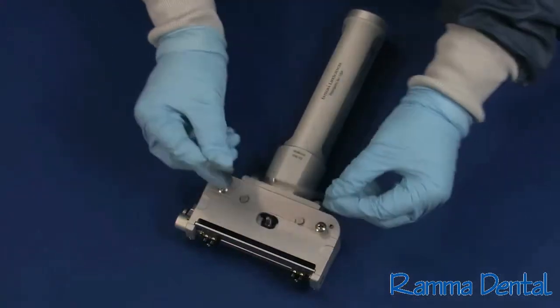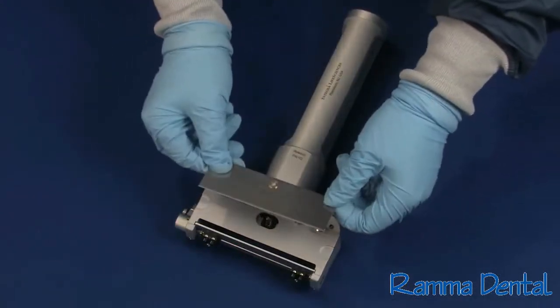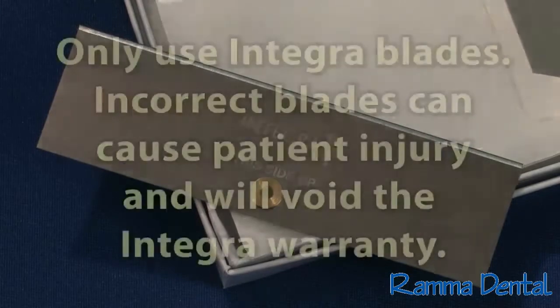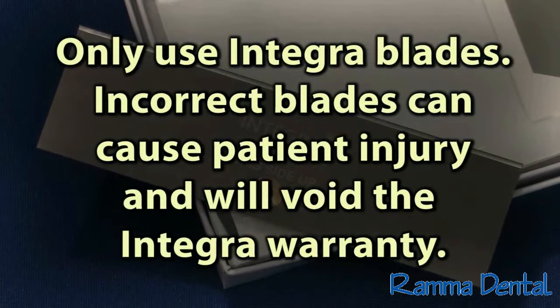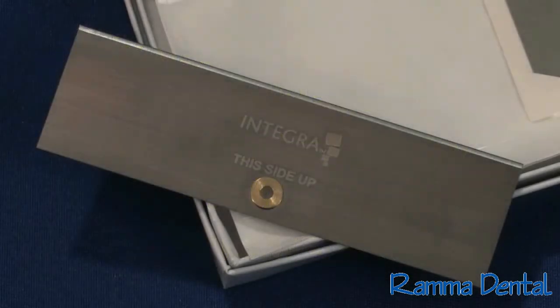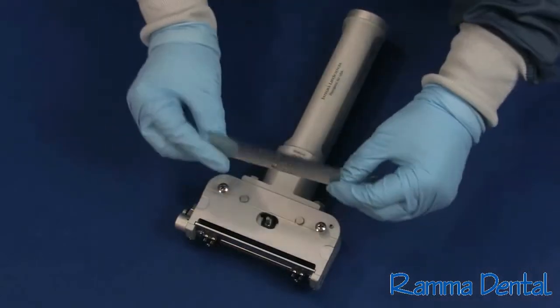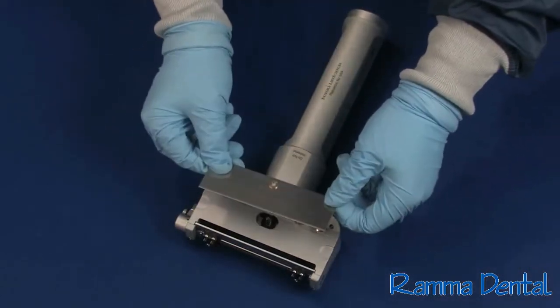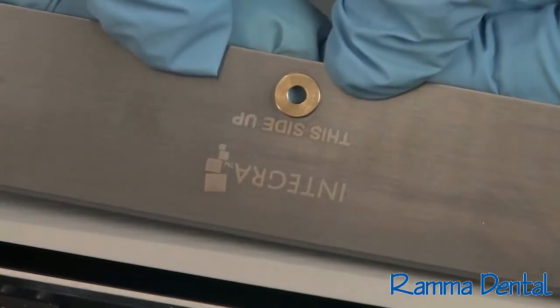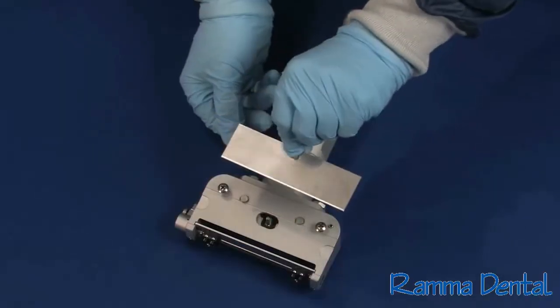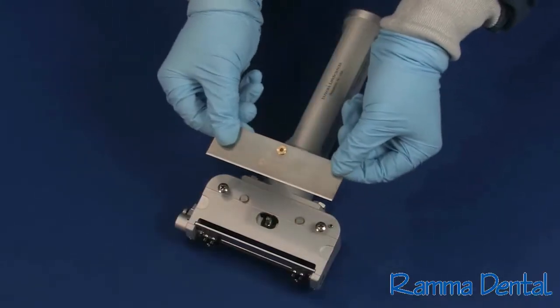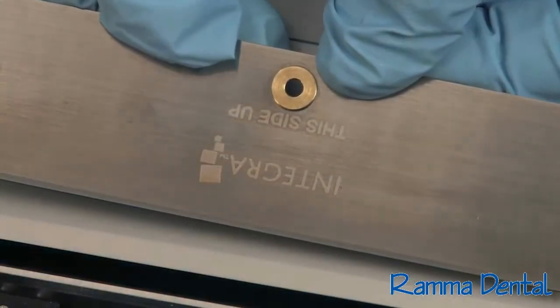We will now demonstrate how to properly install the blade on your Integra dermatome. Please note that Integra dermatomes should only use Integra blades, and Integra blades should only be used on Integra dermatomes. Failure to comply could result in serious patient injury and will void the Integra dermatome warranty. To install the blade, check to make sure that the blade and blade bed are free of any lint or foreign matter. Note that one side of the blade reads "This side up" and features the Integra logo. The other side is blank. It is important to keep the side that reads "This side up" facing you during the installation process.